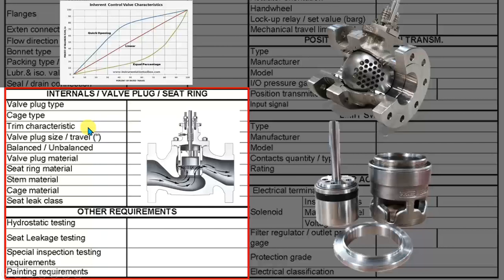Trim characteristics is a key field to specify, as it relates directly to the purpose of the valve. This is simply a graph of valve CV or capacity factor over stroke or valve opening. Using a linear or equal percentage characteristic has been more common, but there are some new designs that can modify the graph based on special requirements. Another interesting concept here is balanced trim — that is one or a few passages between the pressure side of the plug and the back seat cavity up in the bonnet. This feature can balance the force upon the plug and reduce the required torque from the actuator, allowing selection of a smaller one. Designers often use this design in large size linear control applications.